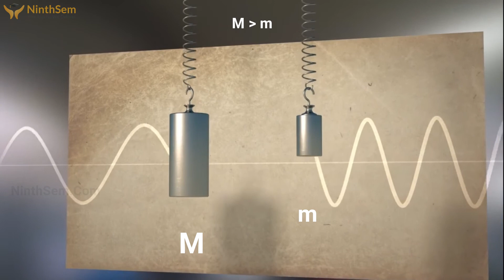For density of flow to be measured, I will give you an example: a higher mass and a lower mass are attached to a spring. If they are allowed to oscillate, which one oscillates more? Obviously the smaller mass will oscillate more than the higher one. Hence it is proved that the tube inside which a less dense fluid is flowing will oscillate more than with a higher density fluid, as I already gave the example of water and gear oil.